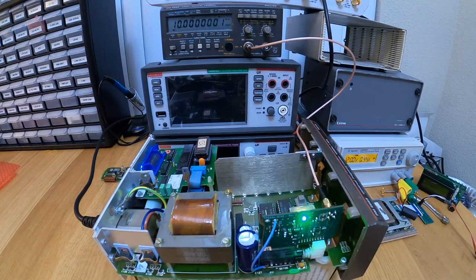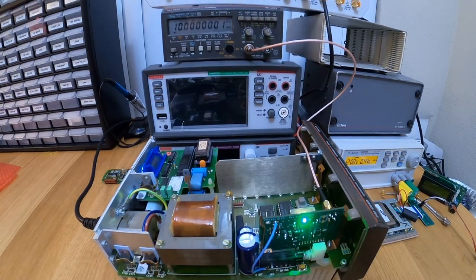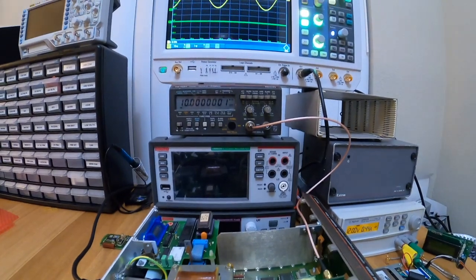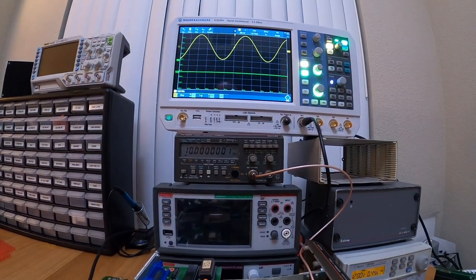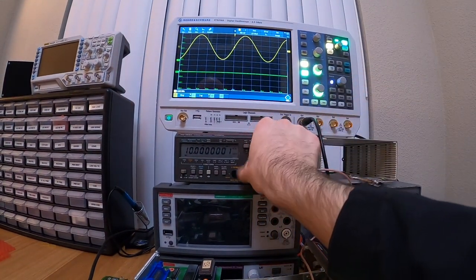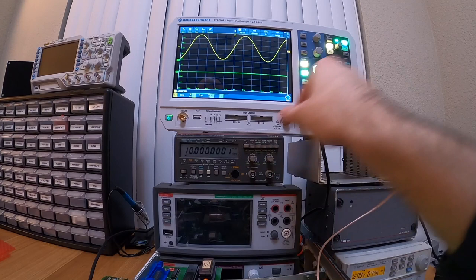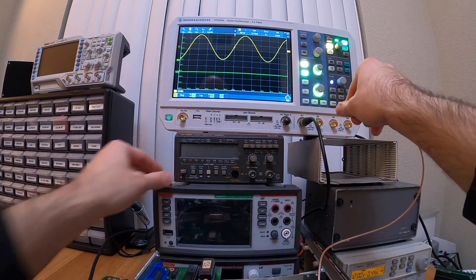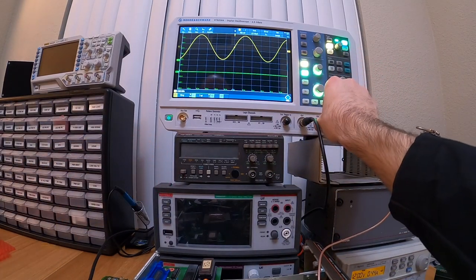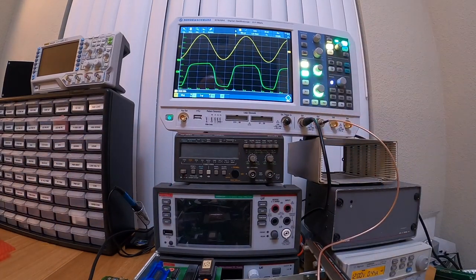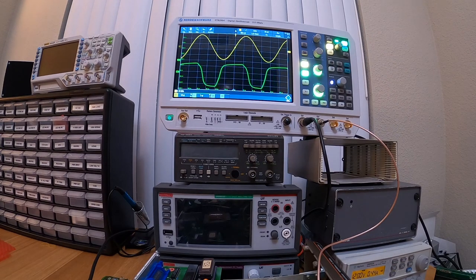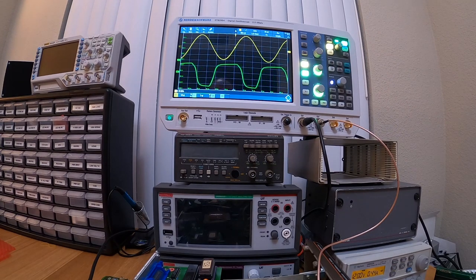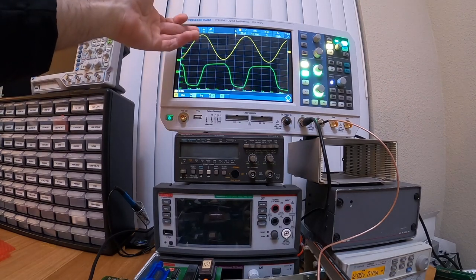And obviously, it's going to be a bit longer, but it will allow me to get a closer reading and a more precise reading. And then I can move to the oscilloscope method. Okay, that should be close enough. So let's move to the oscilloscope now. So let me switch the view here. Grab the signal here. I can turn it off. Put it in there. And yes, we are pretty close to the 10 MHz reference frequency here.